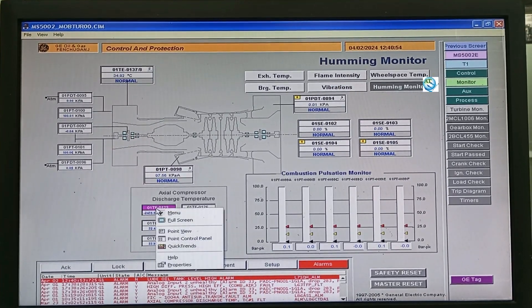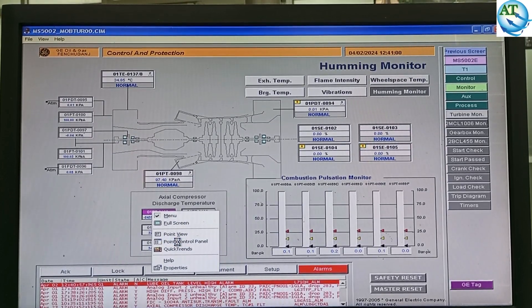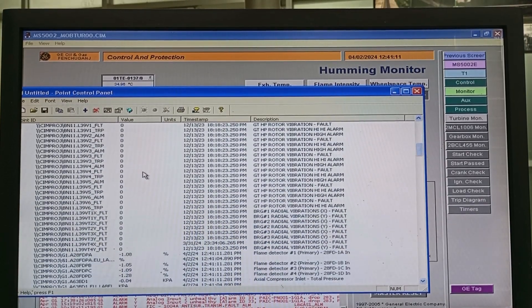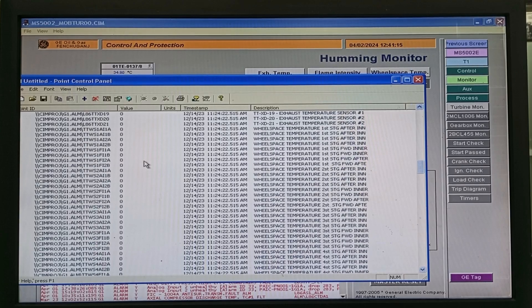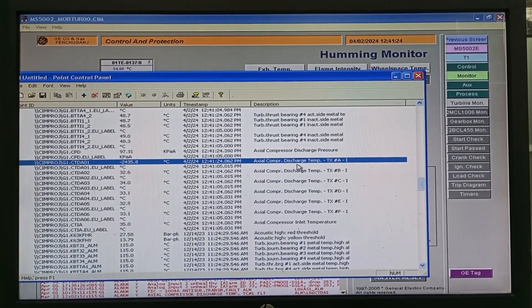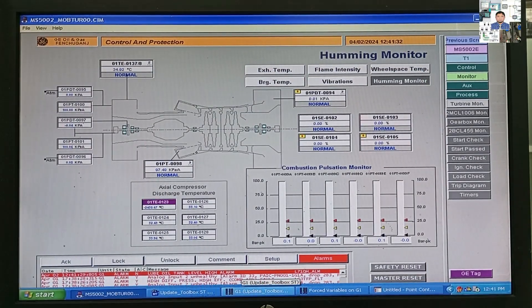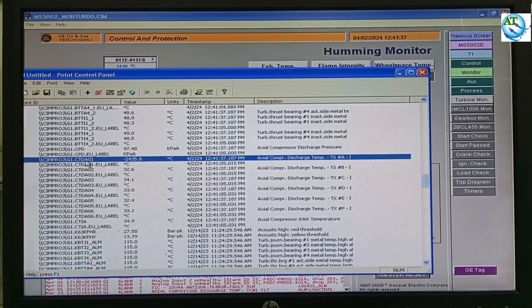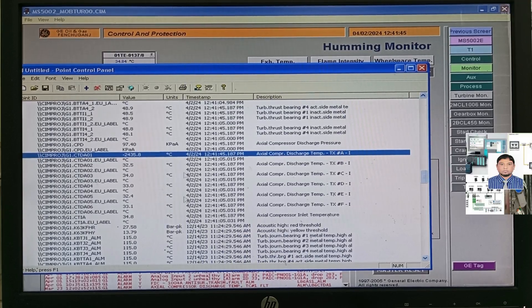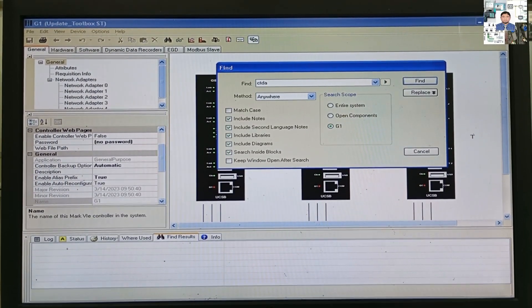At the running condition, if we want to replace this transmitter, we must make a force condition. In the control diagram, click the right button and go to the Point Control Panel. In the Point Control Panel, you can easily find the tag number or control tag of this control system. Here, you can find the desired tag number. This is the controller tag — CTDA01 — which is the tag number. You can use this tag to find the block in the logic system. We will write this in the GE control system to find this block, then we can make the force value.